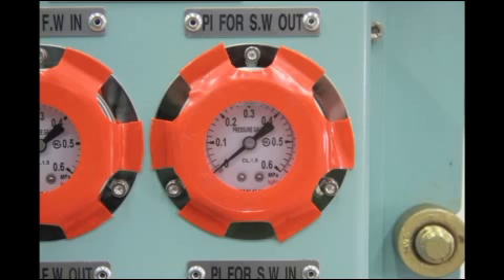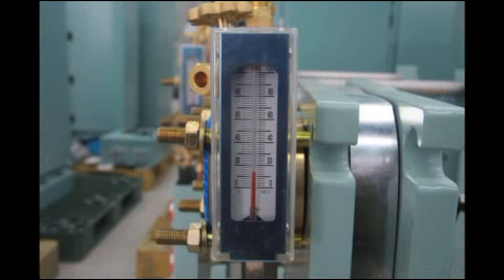Installed in HEU. Check if the pressure gauge installed in both inlet and outlet of seawater and freshwater, cooling water, shows pressure of seawater and freshwater properly. If the temperature of freshwater cooling water is over 40, check the temperature of seawater. Check that HEU shows the temperature of circulating seawater and freshwater properly.